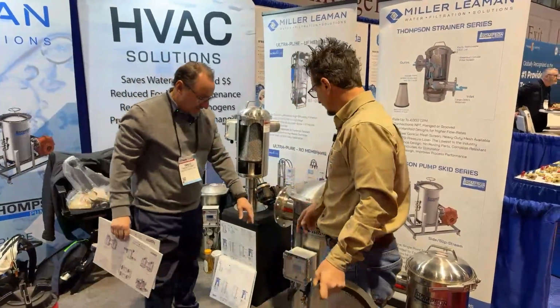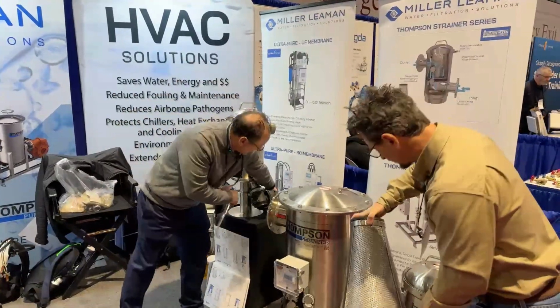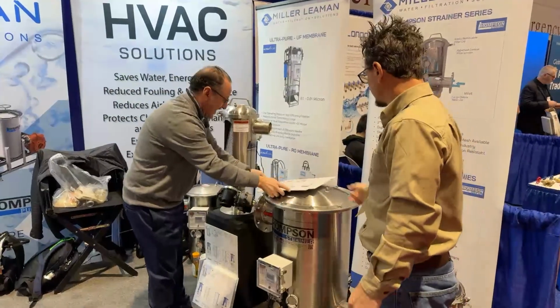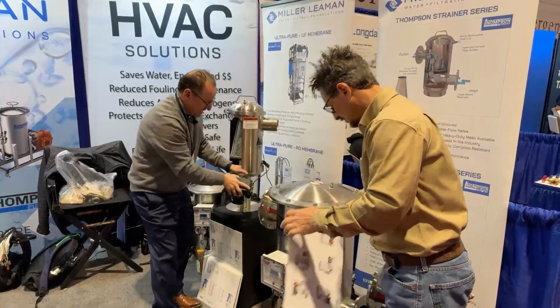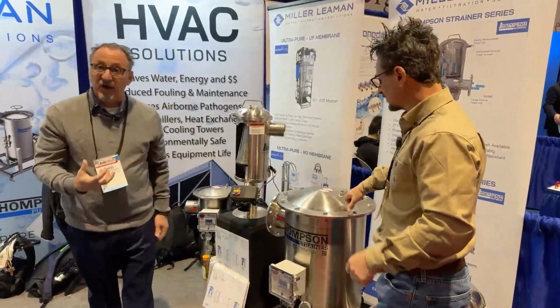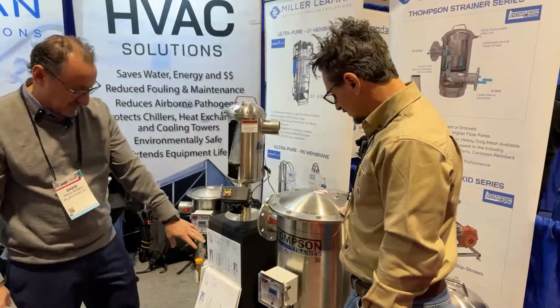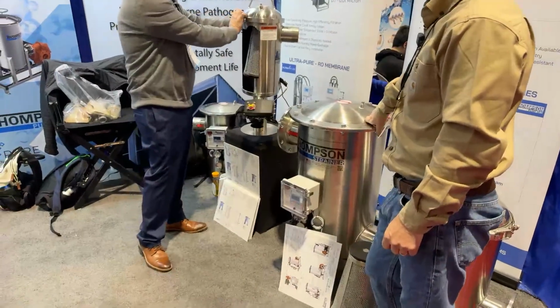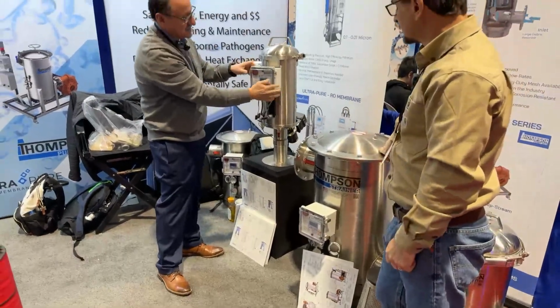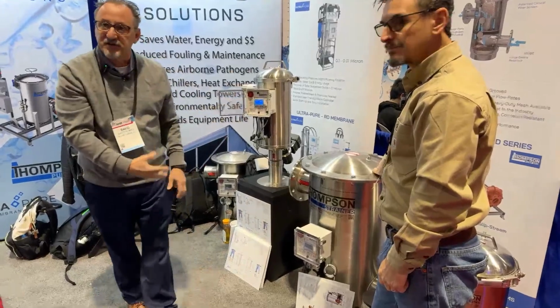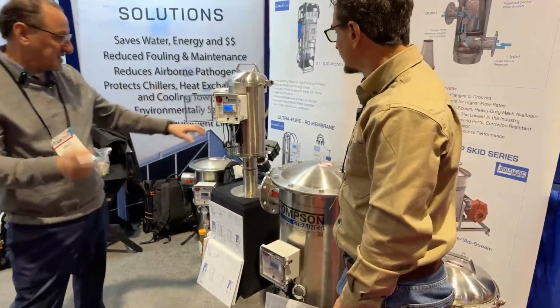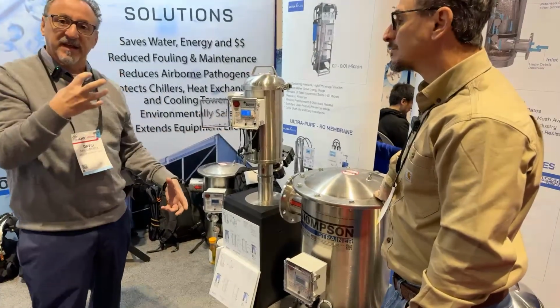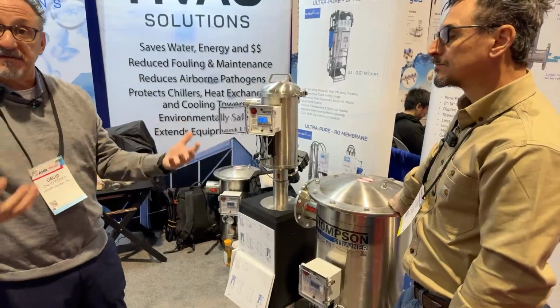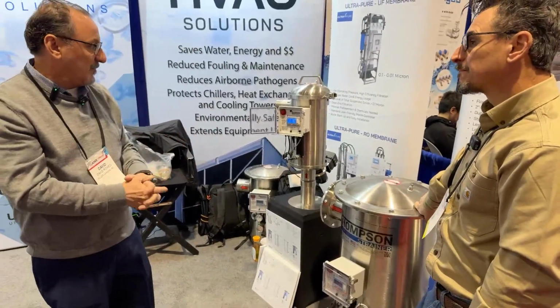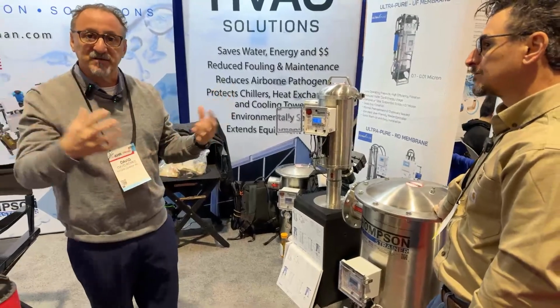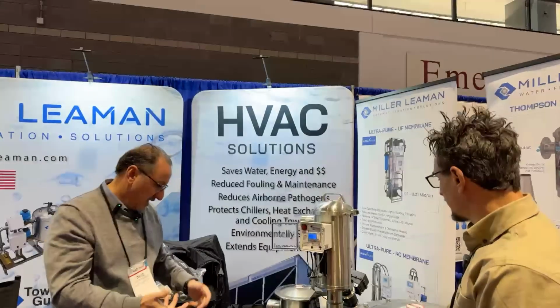There's an automatic timer flush, which is this valve right here, which will automatically flush it under flow and under pressure. And then we have a pressure differential alarm, which will monitor the inlet and outlet pressures of the system using transducers, so it's extremely accurate. It's going to tell you the inlet pressure, the outlet pressure, and then the differential of that. And you can set it up where it'll alarm out when the pressure differential gets too large. Nice. Fully automatic if you want it.